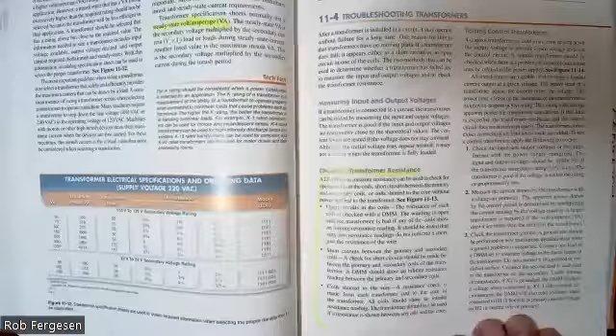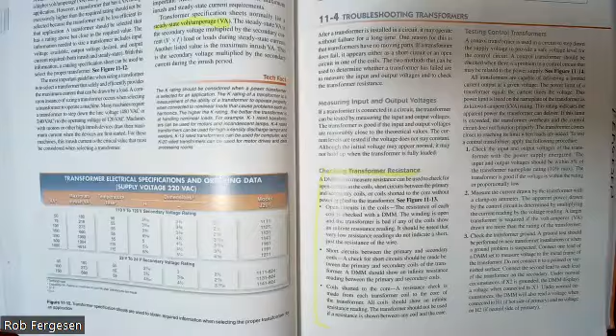I will also mention that on page 233, this section on troubleshooting transformers is excellent. If you find that any one of these coils, if you disconnect your wires to it, right? You disconnect these wires, and if you find that you have that coil open, like there's no continuity at all, then you've got a problem with that transformer. That means that coil's burned out. You need to check all the coils separately when you're checking for continuity. Second thing is you might have a short.